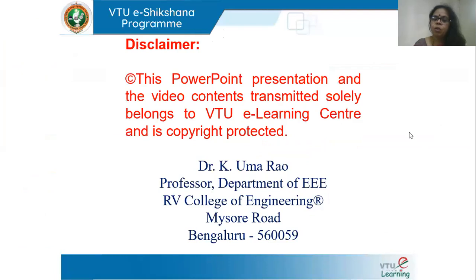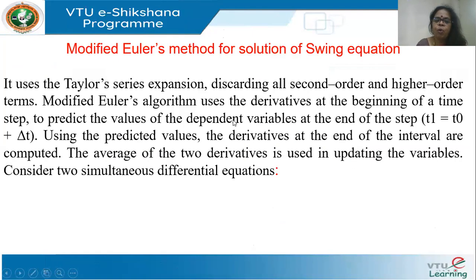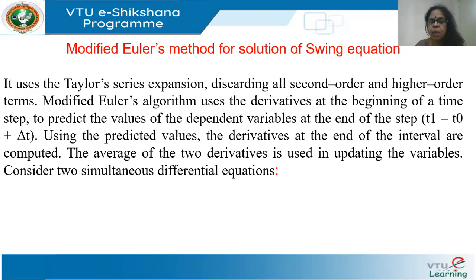In this talk, we will cover the modified Euler's method for solution of the swing equation. We have already seen the Runge-Kutta method, and now we take up the modified Euler's method. We use numerical methods for the solution of the swing equation because it is non-linear. Modified Euler's method is also very simple to program and hence quite popular. Similar to the Runge-Kutta method, it uses a truncated Taylor series expansion, retaining only the first order term and discarding all second order and higher order terms, making computation very simple and fast.